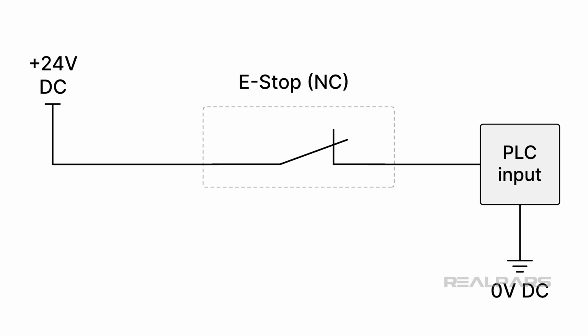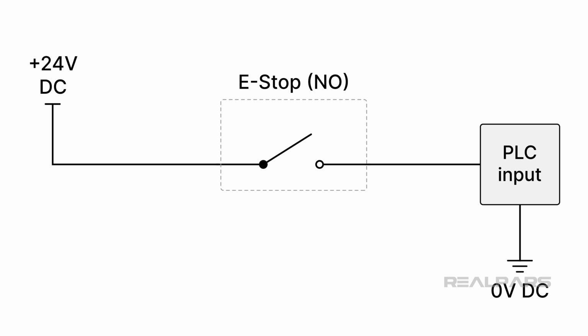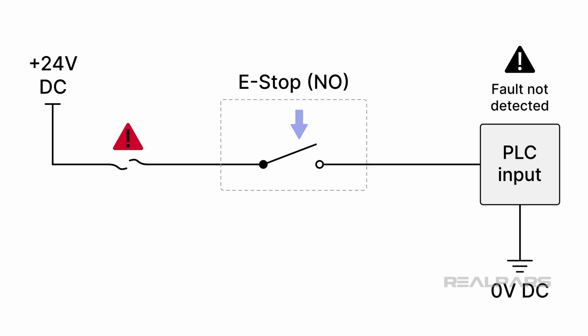Why? With a normally closed switch, voltage is normally present throughout the circuit, providing proof of circuit continuity. If an open circuit occurs due to a broken wire or a defective switch, it is detected quickly. If it were a normally open or NO switch, power would be applied only when the switch is operated. An open circuit fault would not be detected until the switch is operated, which is unacceptable for obvious reasons.